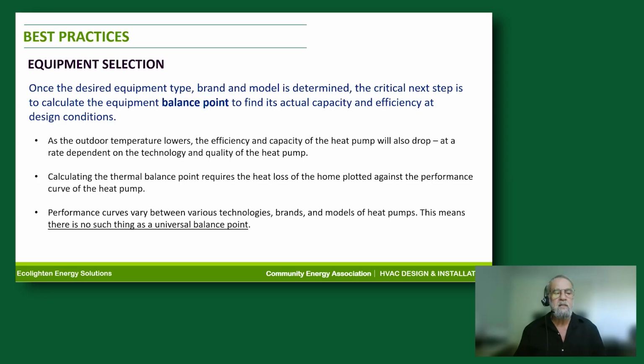Calculating the thermal balance point requires just the heat loss of the home plotted against the performance curve of the heat pump. Now, I don't want to get into that too much because that's into the technical weeds and we could spend a whole day talking about that. But just at the high level, a balance point has to be done. That's the thing to take away from this. And here's another thing. I've often heard that a heat pump works to this degree, and then you need your auxiliary heat or supplemental heat, your backup heat, however you want to call it. But that's actually a myth. There's no such thing as a universal balance point.